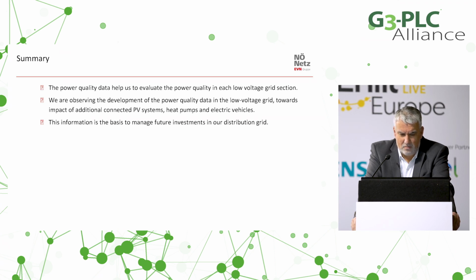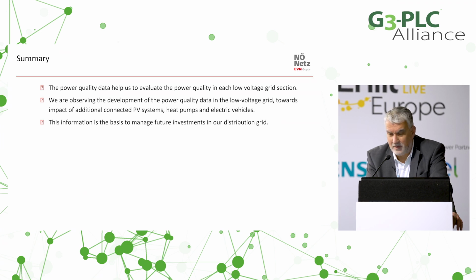On one side, if we have too many PV systems, maybe on a Sunday afternoon with low load in the grid, we get overvoltage. We see that heat pumps and electrical vehicles will increase in the future, and we have to control how we can handle this. It's always focused on one substation area, and it can be different from substation area to substation area. All this information is the basis to manage future investments in our distribution grid, to focus on where we will have problems and make the investments. Thank you very much for your attention.